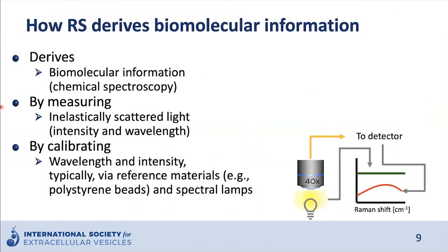To recap: Raman spectroscopy derives biomolecular information of the interrogated sample by measuring inelastically scattered light to form a spectrum plotting intensity versus wavelength, or energy of the scattered photons. To reproducibly collect such information in a calibrated manner, you have to calibrate both the wavelength — usually by using a known reference material like polystyrene beads or toluene — and also the intensity, usually calibrated by the use of NIST-traceable spectral lamps, which themselves have to be calibrated on an annual basis.